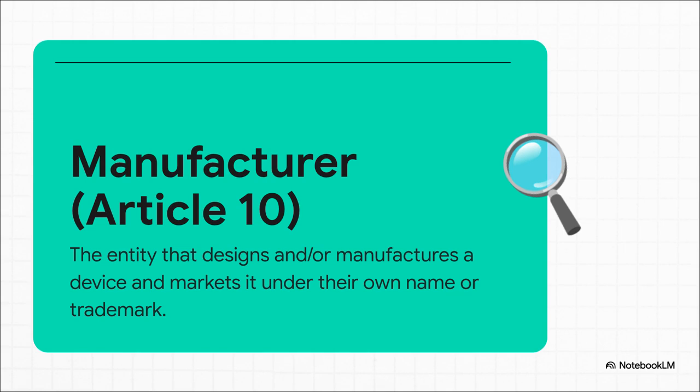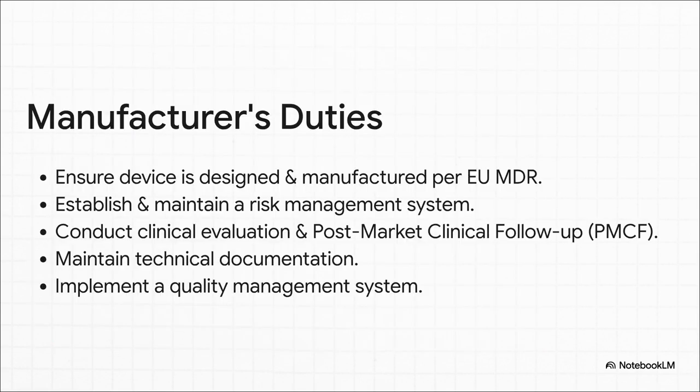This is the entity that has the primary and, frankly, the most extensive responsibility for the device. From that initial spark of an idea all the way through to post-market surveillance, the buck really does start and, in many ways, stops right here. So the manufacturer's duties, all laid out in Article 10, are just immense. I mean, this isn't just about building something. It's about proving it's safe through really tough risk management and clinical evaluation. That includes an ongoing post-market clinical follow-up, or PMCF. You're also responsible for all the technical documentation, the quality management system, basically the whole shebang. And at the end of the day, you assume the liability.